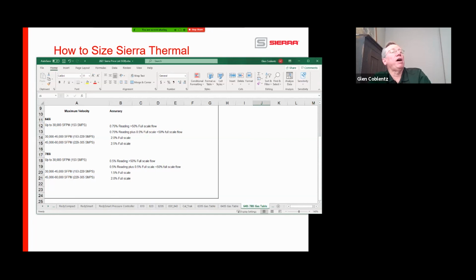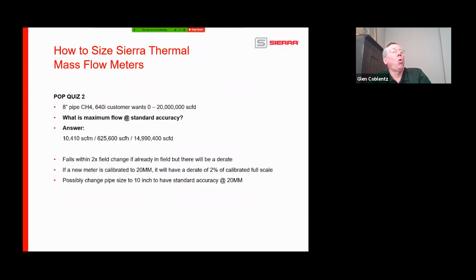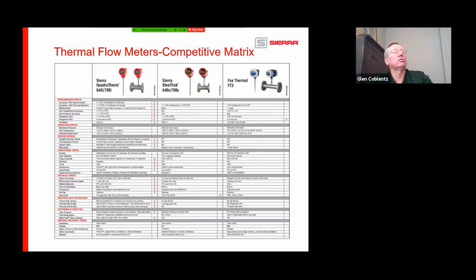30,000 to 45,000 standard feet per minute gives you 2% of full scale. So they could have it calibrated that way to start with. Or they could possibly change the pipe size to 10-inch and have standard accuracy at 20 million. So again, we're going through this process to find minimum and maximum flow rates, comparing them with what the customer wants to see what's going to work and what might have to change. And I appreciate all those that were playing along on the home game, coming up with these various different answers. It's good to see.